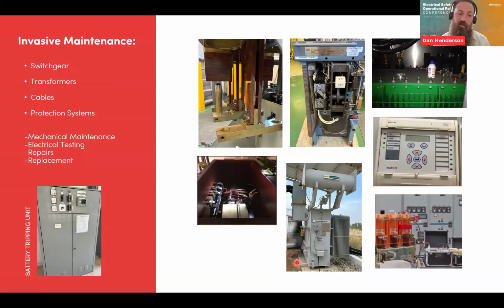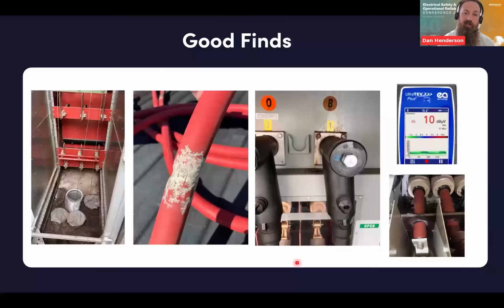And just finally, the battery tripping units. Again, can't emphasize, this is your opportunity. You've got your shutdown. Do your maintenance on your batteries. Replace your batteries if you need to, or maintain them, top them up. Whatever you need to do to make sure that they're functional, because it's the most important bit of kit in that substation. Any changes to your protection, get it done. Trip time test your breakers. So this is your opportunity to get all those prescriptive elements done physically.